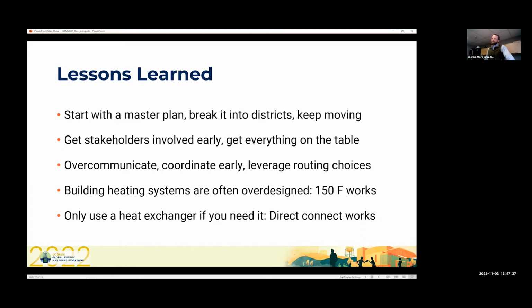A couple more technical points. We get a lot of questions about temperatures. All of our building systems until recently were designed for 180 degrees maximum heating temperature for the heating hot water systems. A couple years before implementation, we turned them all down to 150, 155 maximum. We knew our maximum hot water temperature on the loop would be 160, so we wanted to see how buildings would do with that as their max. What we found in general is that 150 Fahrenheit works for heating buildings, at least in California. I can't speak for other places, but a lot of these systems are over-designed on the heating side, with two-row coils and more heat than they end up needing. Where we did have problems, it was often a plugged strainer or airflow issue, not a temperature issue, so I wouldn't worry too much about that, at least with our kind of climate.